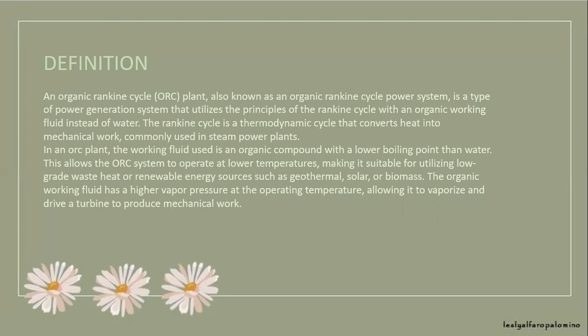In the Organic Rankine Plant, the working fluid uses organic compounds with a lower boiling point than water. This allows the Organic Rankine system to operate at lower temperatures, making it suitable for utilizing low-grade waste heat or renewable energy sources such as geothermal, solar, or biomass. The organic working fluid has a high vapor pressure at the operating temperature, allowing it to vaporize and drive a turbine to produce mechanical work.